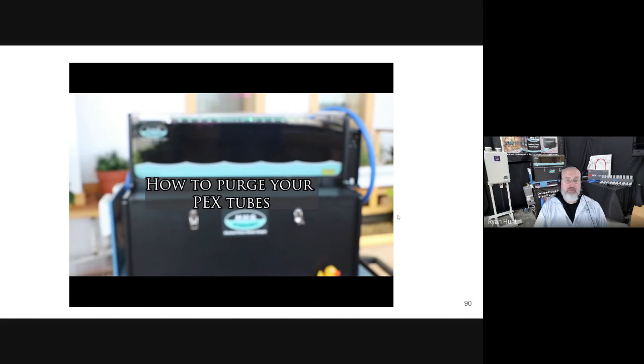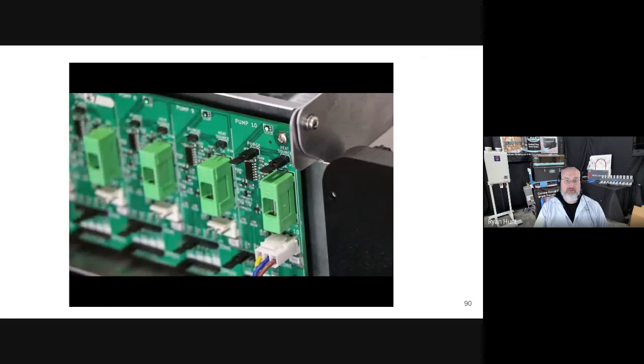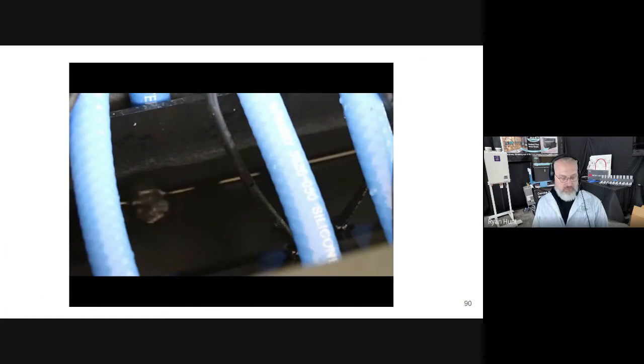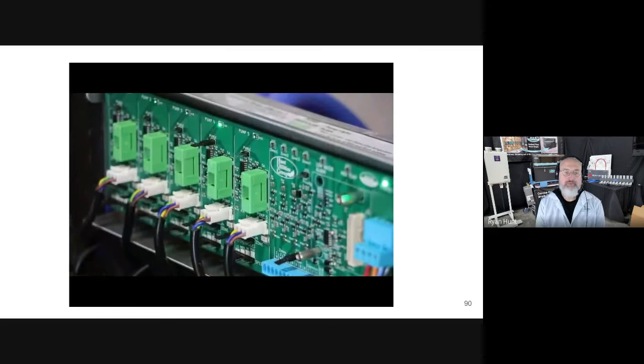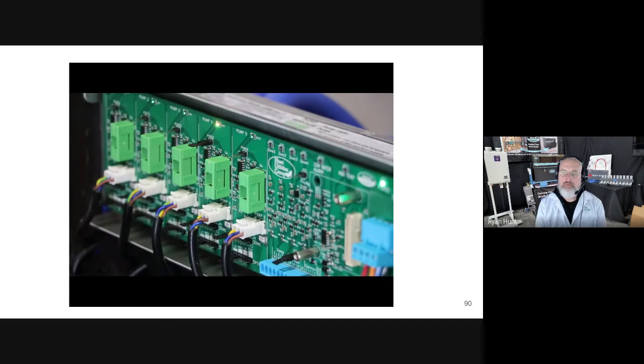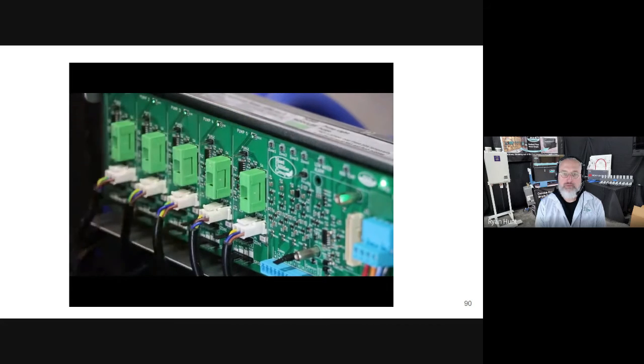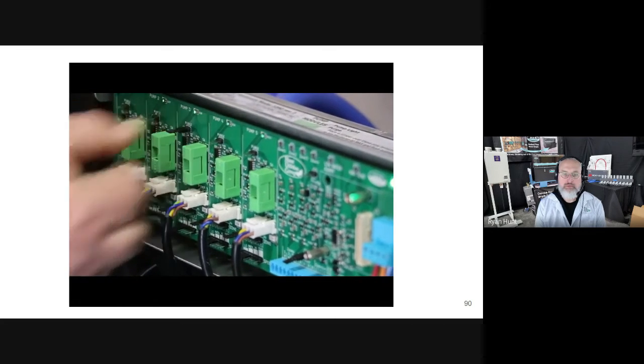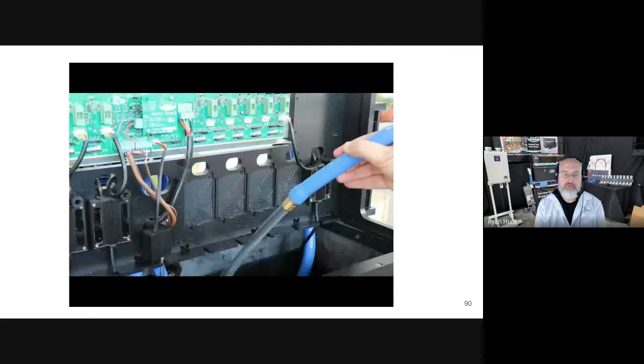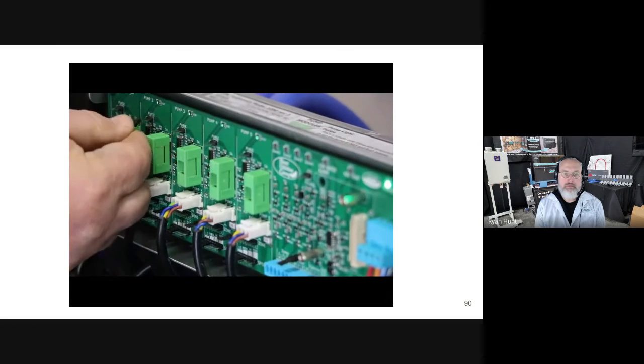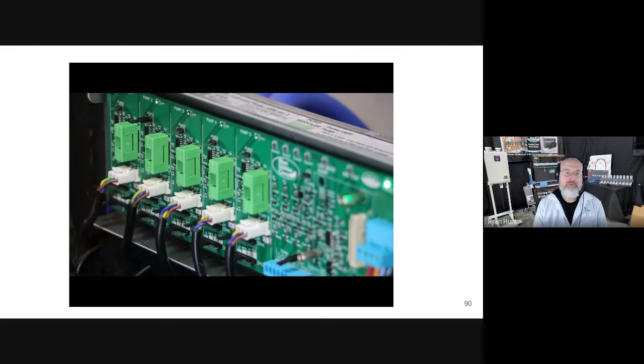Now we'll purge the air out of the heater and pipes. Place a spare jumper on the purge pins for pump 10. The pump light should become bright yellow. Let the pump run until the gurgling sounds in the water tank cease. Repeat the purging process for each pump that is in use, one at a time. If the tank becomes low during this process, add more water to the tank as needed. As a note, each 300-foot PEX loop holds about 3 gallons of water. Then, return the spare jumper when complete.